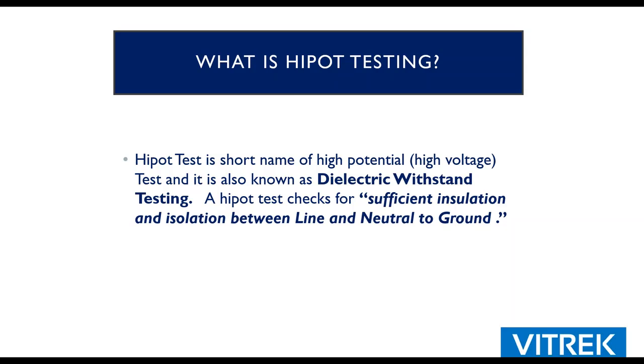Basically, it is a test where you put significantly more voltage, let's say 10 times more than a circuit would typically see, but not across the circuit. You're applying voltage to the circuit, and then you're measuring that leakage to ground or chassis. So it's really an isolation test, just to verify that there's sufficient insulation and isolation. And that can be plastic, air, ceramic. There's all kinds of different insulators out there.